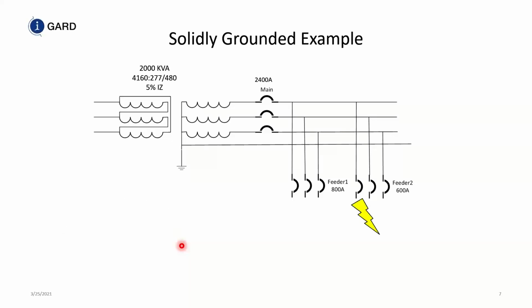If you get a ground fault on one of the phases, the ground fault current can be as high as 34,000 amps. So obviously it's going to be greater than 3,000 amps. But this is the maximum current that can flow in a single phase to ground fault if one should happen at this location, and not including an extraordinary amount of impedance in the fault.